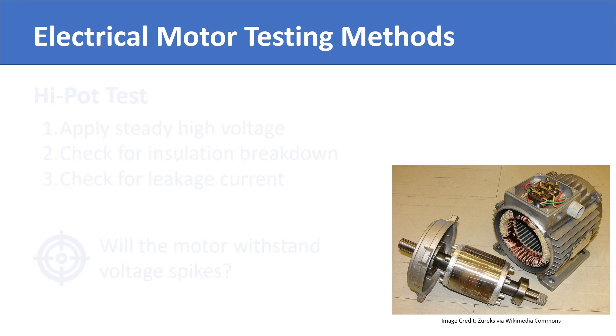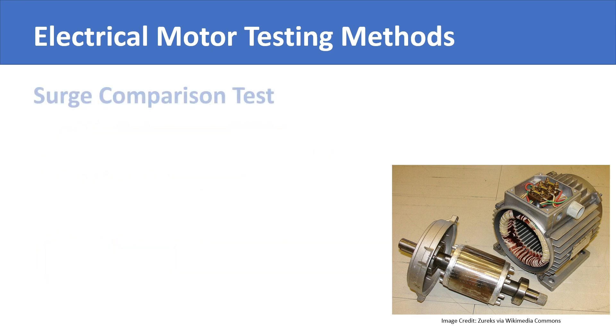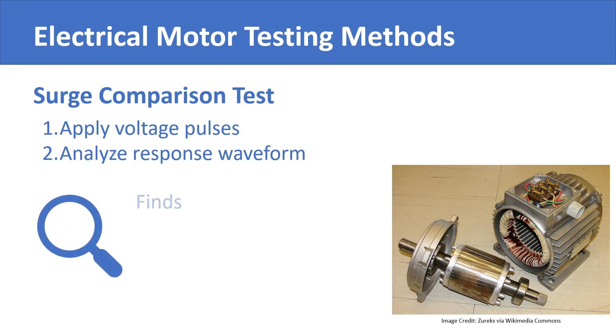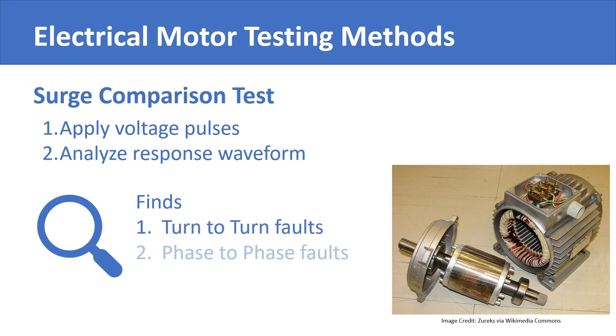Another similar test is known as the surge comparison test. It is like the high pot test except that it uses voltage pulses instead of a steady state voltage. It then analyzes the response waveform of the pulses to detect any anomalies in the winding insulation. It may be used for testing turn-to-turn faults, phase-to-phase faults, or insulation degradation.